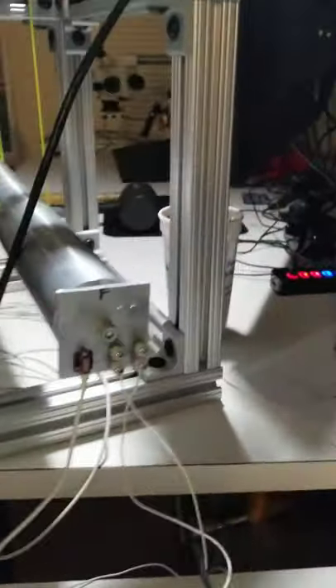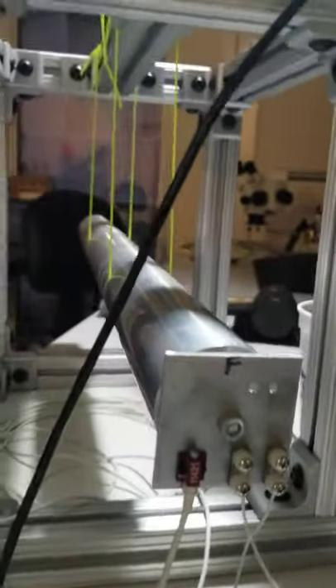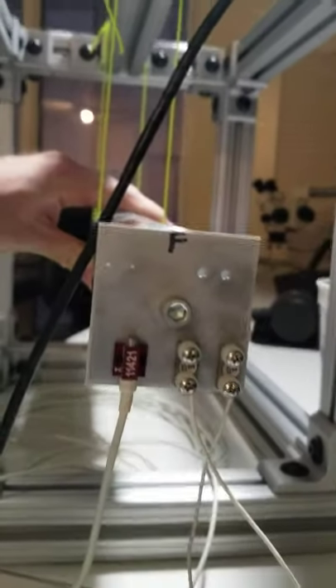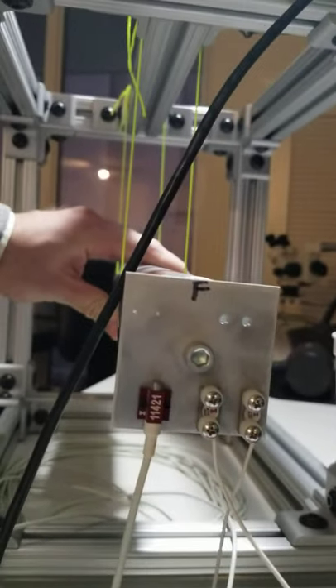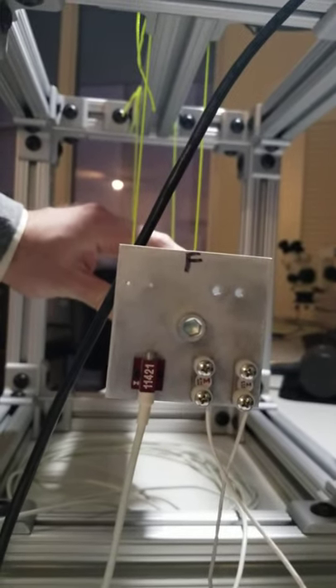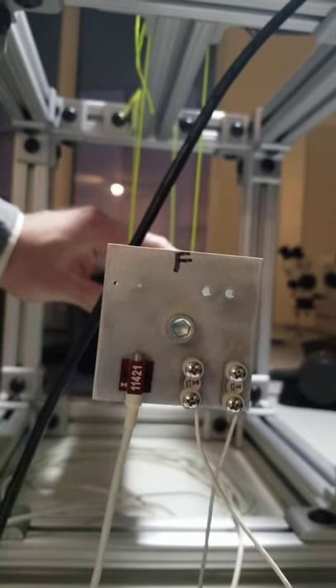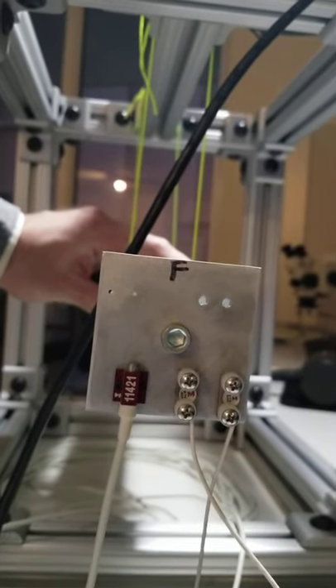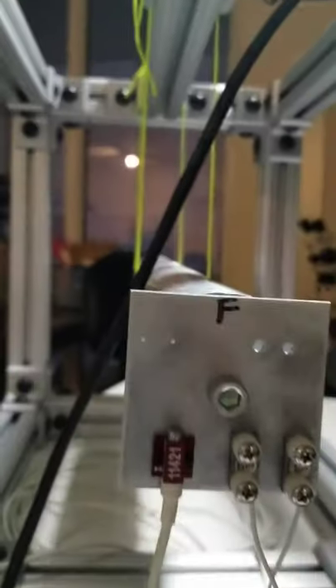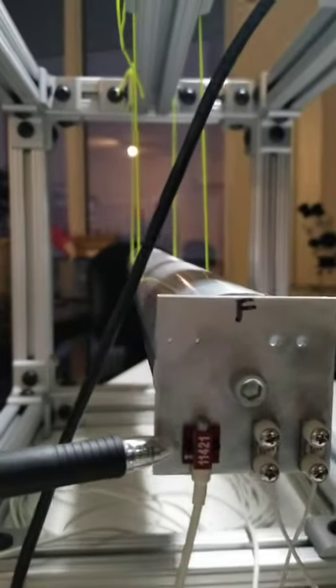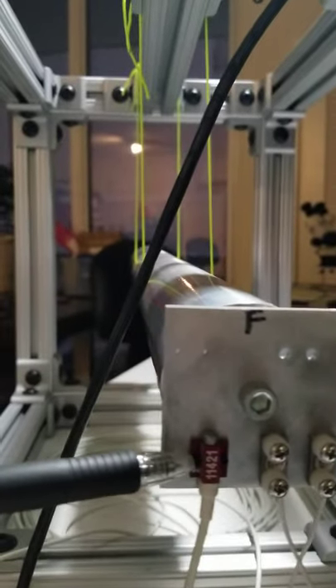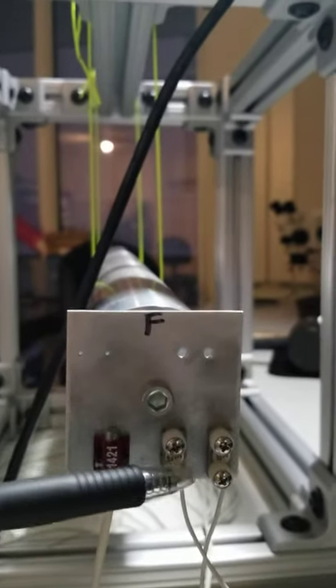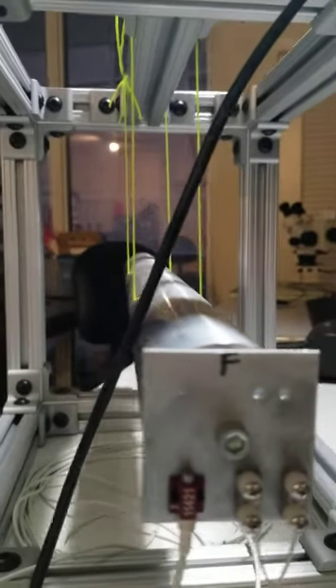On the front end for these tests, especially in the overview series, any accelerometer test will consist of these three. It's an Endevco 7264H and two 7270A60Ks, so there's a 1000g accelerometer here and then two 60Ks mounted here.